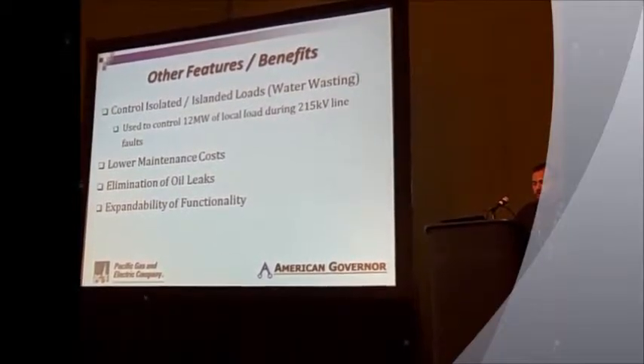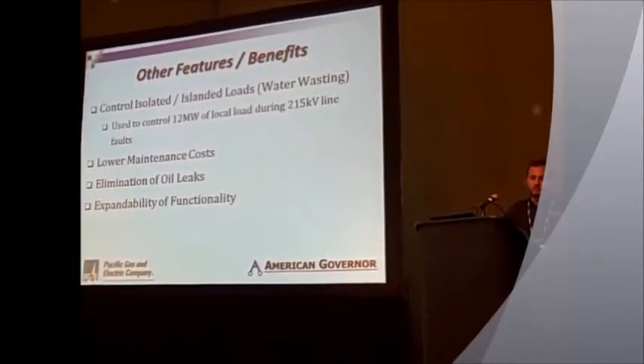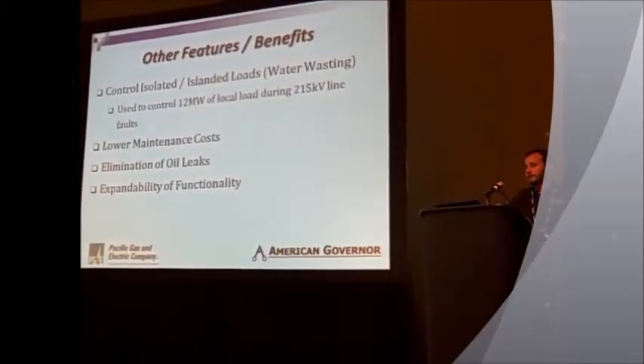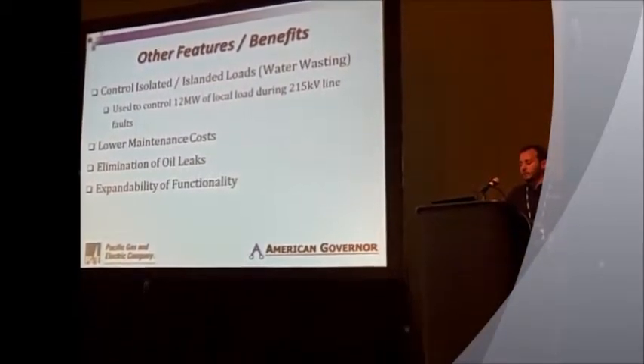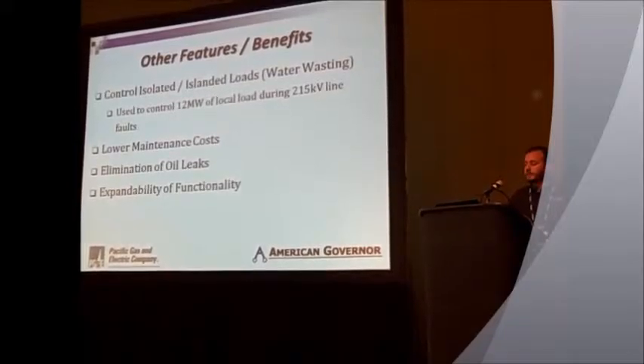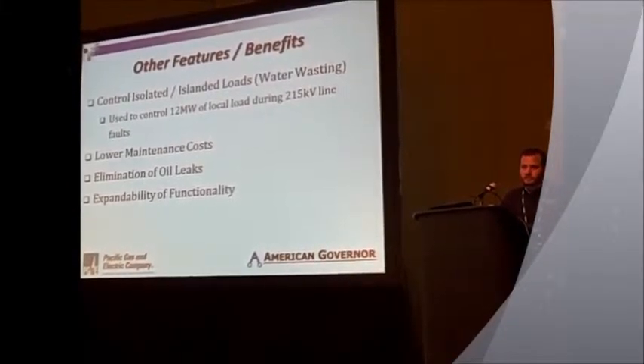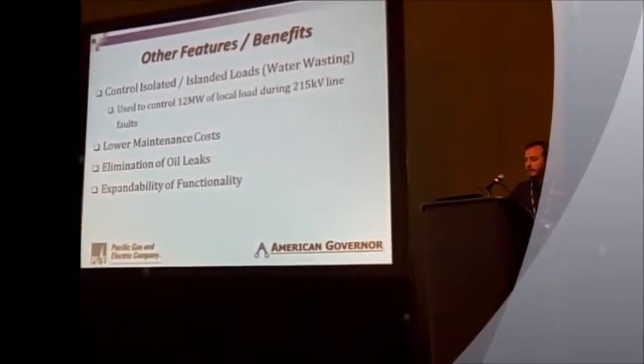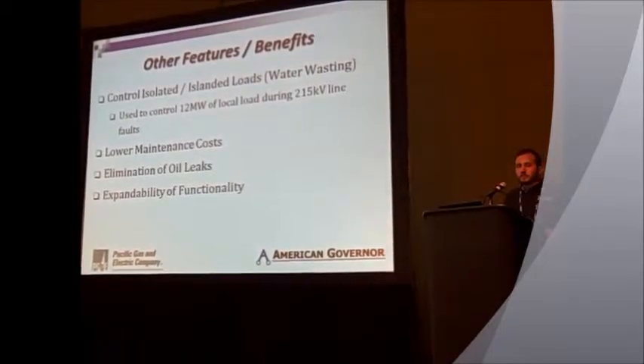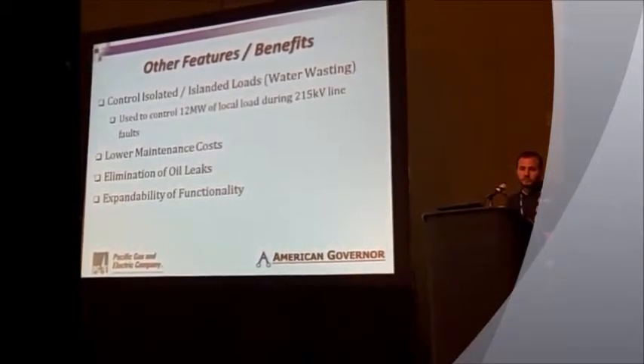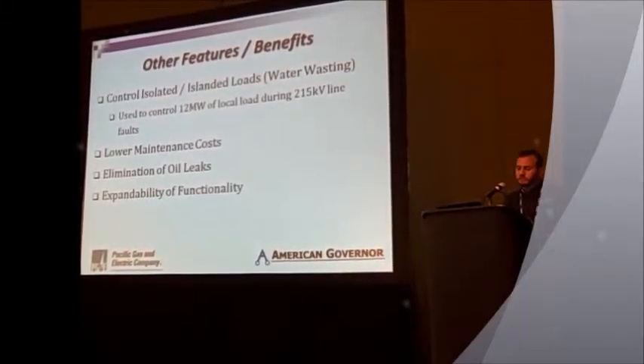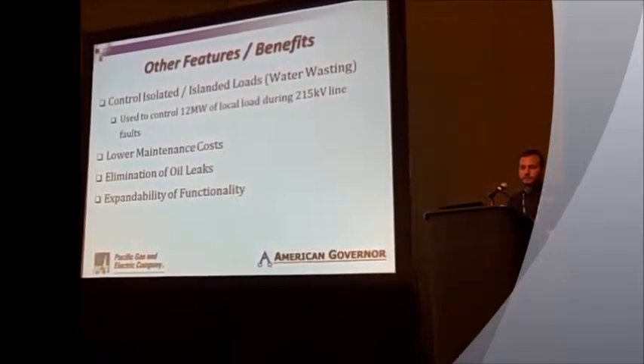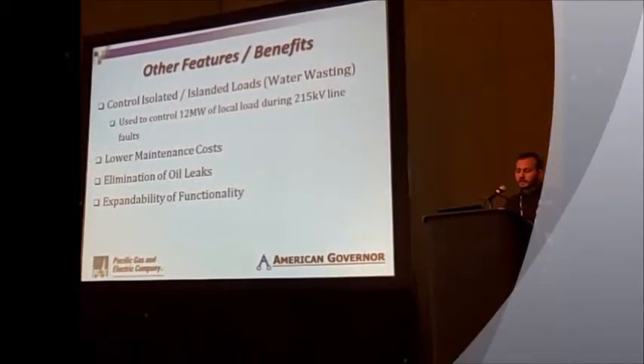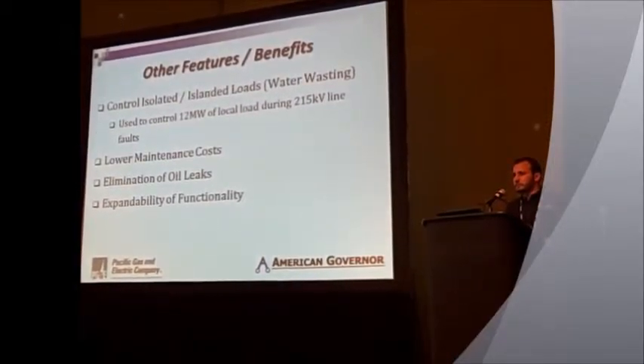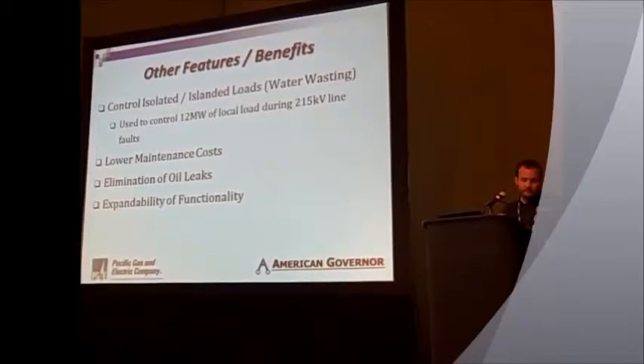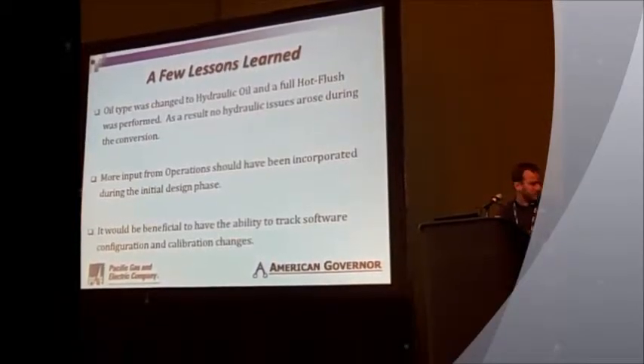Additionally, there are lower maintenance costs for this equipment, mostly from not needing to do calibration as frequently, and parts, pins, and linkages not wearing out. The elimination of the oil leaks is a welcome benefit. And in the future, if any expandability is required, such as forebay level control or afterbay level control or downstream control for any kind of cascaded river management, that would easily be added to the system because of the digital nature. So with that, how are we on time?